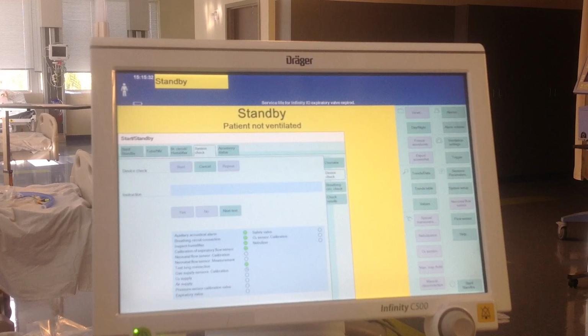Unfortunately, there's no way around these. If you do not do a pre-use calibration or pre-use check as designated by the manufacturer, and you put it on a patient and something happens, it could then be not good for you or the hospital. All of these ventilators have memories, and everything on the computer is stored. Bioengineering can go in and see all the checks for like the last year. This is the longest part of the test. It takes a few minutes.